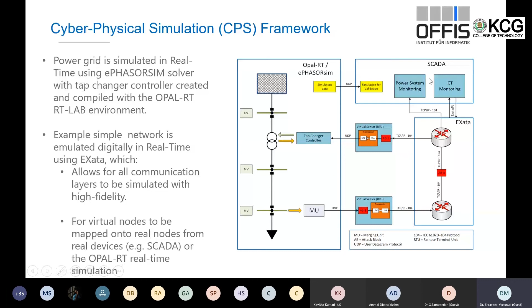So what is the application here? Normally, if you take any tap change transformer, the typical voltage range should be between 0.97 and 1.03 per unit. It is typically defined that if the output of the controller sensor senses the voltage is within this range, then no action needs to be taken. But if the voltage is beyond this threshold for a certain period of time, then the controller sends a corrective action. What is the corrective action? The corrective action is to change the step of the tap change transformer, either upwards or downwards. There are plus 16 or minus 16 steps, so you either increase or decrease the voltage depending on the phenomenon. That is the typical behavior.